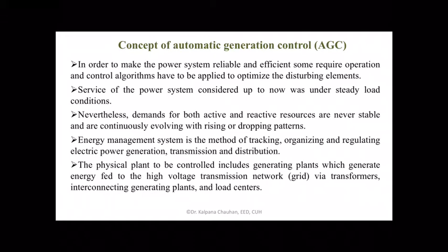Now, since the transmission systems have negligible energy storage, either generation or demand must be balanced, supply or demand. If we are talking about steam generators, production at the generating plant is controlled by turbine governors and the control center, which are computer remote centers from the generating plants. And these computer remote centers, we also call them central controlling rooms. They generate the command for the generating plants and perform automatic generation control. This is all part of the automatic generation control.